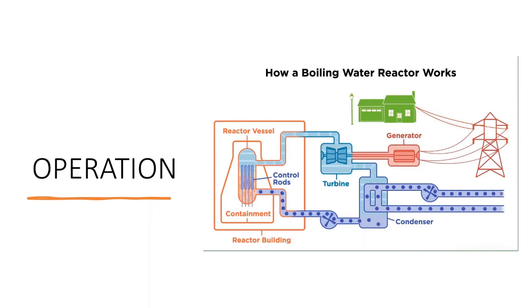The steam is later on cooled back into process water in the condenser located under the turbine. The condenser uses cold seawater to cool the steam down. The warm seawater is drained back into the sea from the condenser. The process water is pumped back into the reactor by a feed water pump.